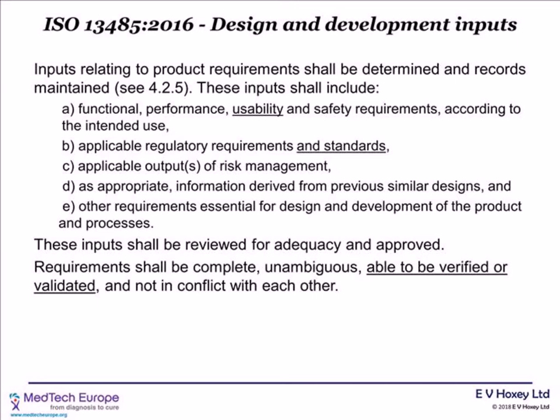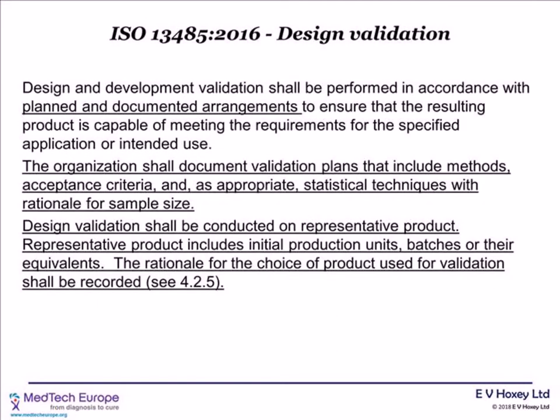Looking in a little bit more detail, the design inputs now explicitly cite usability and applicable standards as design inputs. Then as the design process moves through, you need to see how those inputs are addressed as outputs and verify and validate that the outputs meet the inputs. And a little bit more detail has been added on the design inputs requirements. They need to be not only complete and unambiguous and not in conflict with each other, but they need to be able to be verified or validated.